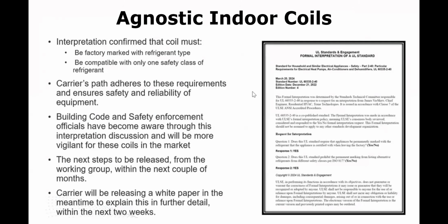And that coil, when it's sold at the counter, the purchaser of the coil, the contractor, could say, I would like that with an R22 piston, please. I would like that with a 410A TXV. I would like that for R32. I would like that for 454B. So one coil, and they tell you what kind of refrigerant they're going to use, and then you would hand them a TXV that they would field pipe on there. And if they bought a flammable refrigerant, you'd also have to hand them all the safety controls. That's the idea with that ADP flex coil.